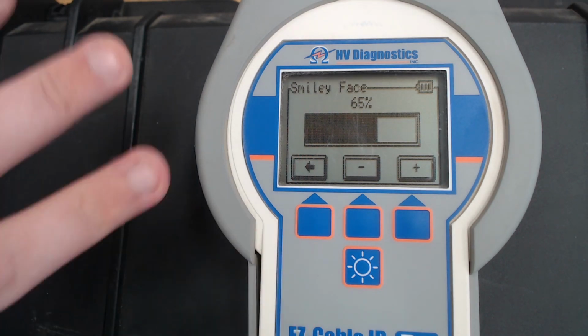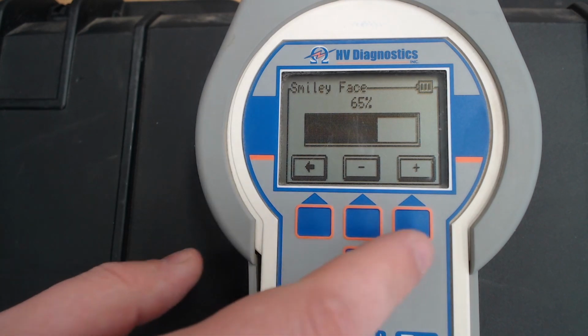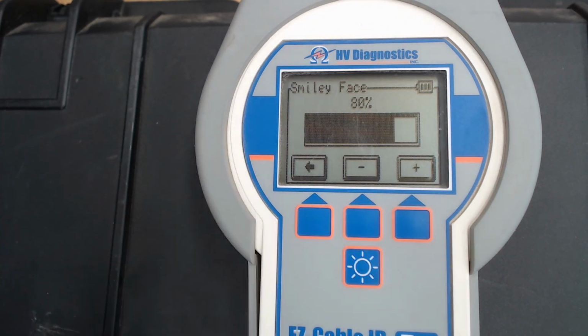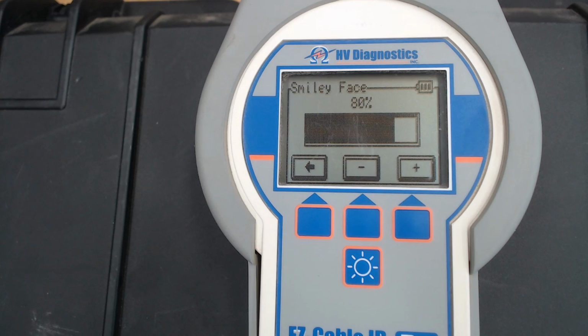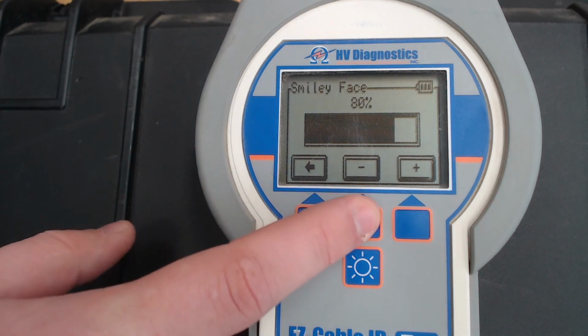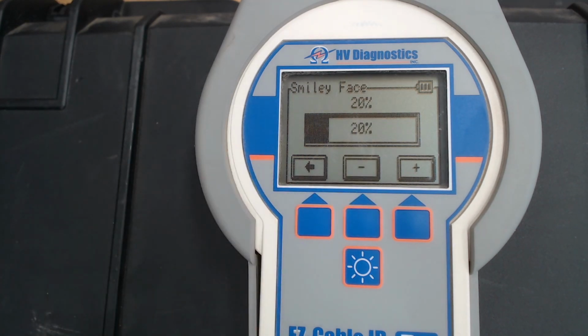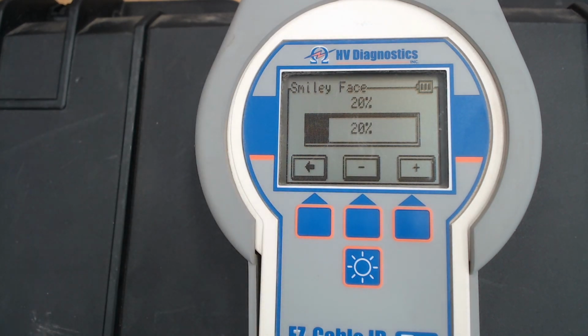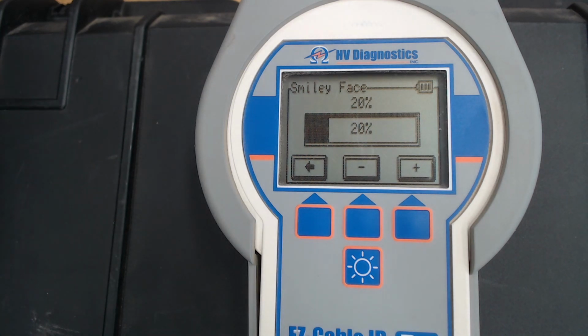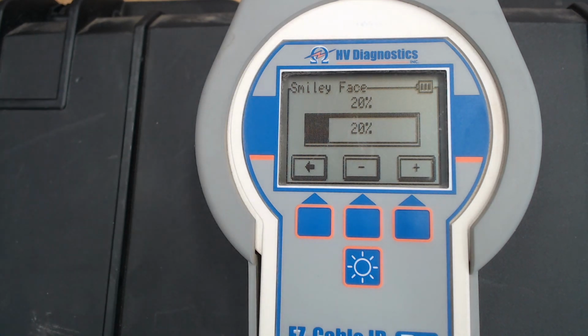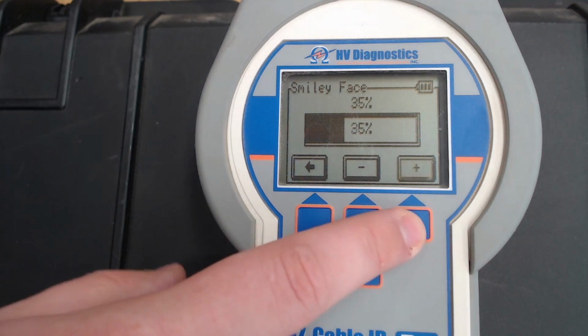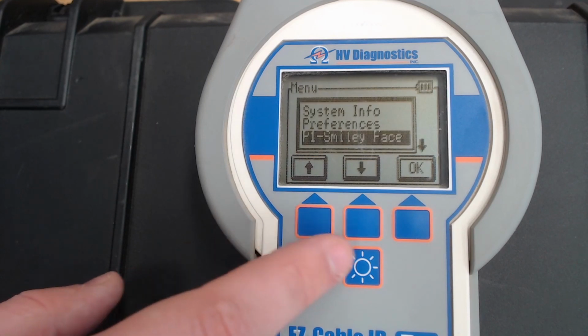So 65% is just what we had set here. If I wanted to take this higher and say I need 80%, it's going to look for that unique signal and 80% of the current that I calibrated with. If you want to go lower, say I only want to have 20% of the current, then on that 10 amps, if I only got 2 amps, that'll be just fine. It'll still give me the smiley face. So that is how to adjust the settings of the calibration mode, how to turn it off, and how to adjust the level. Now we're going to go back down to the next one.